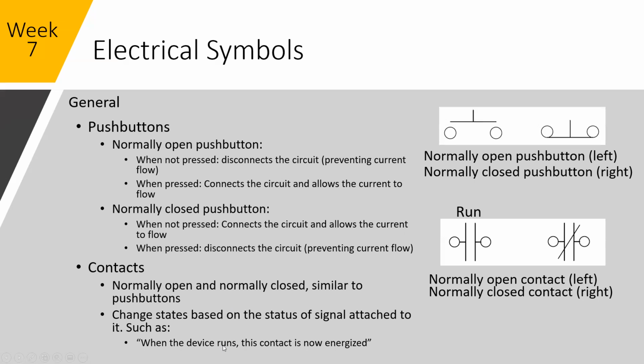So when a device runs, if you've got a motor starter, the motor starter is going to have an auxiliary contact. When the control circuit tells the coil to pull in, it'll pull in, the device will start, and the external run contact will go from an open state to a closed state. It could be a fault contact. If you've got a level transmitter that has an analog signal, but also, if it's an ultrasonic, a fault indicating the ultrasonic transmitter is not working properly, you could have a contact that indicates that coming back to the PLC. Any questions?